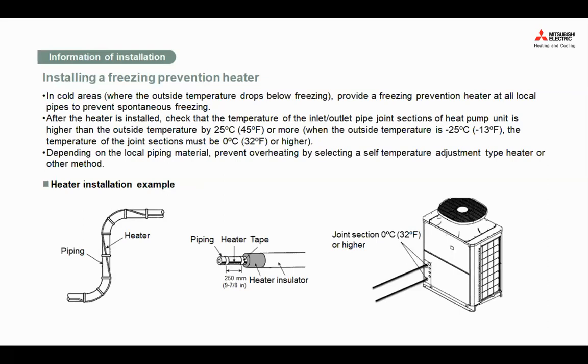And on top of that, I think a lot of us are very familiar with the concept of heat trace, right? Especially, I remember the cold weather, let's say in the colder regions. We will wrap the heat trace cable around the pipe, around the joint, just to prevent the water from freezing. And there's also self-regulating cable, where the resistance or heat capacity will increase or decrease depending on your pipe temperature, so the touching surface temperature increases or decreases to keep the water from freezing. And also you want to make sure the joint is above 0 degrees C.